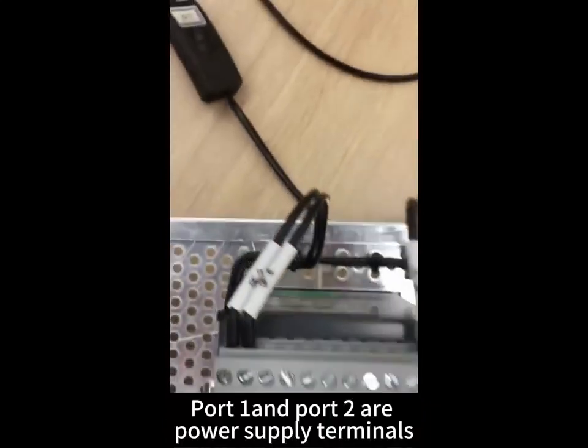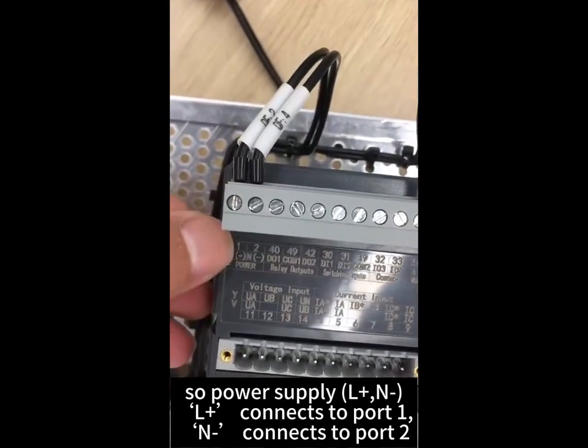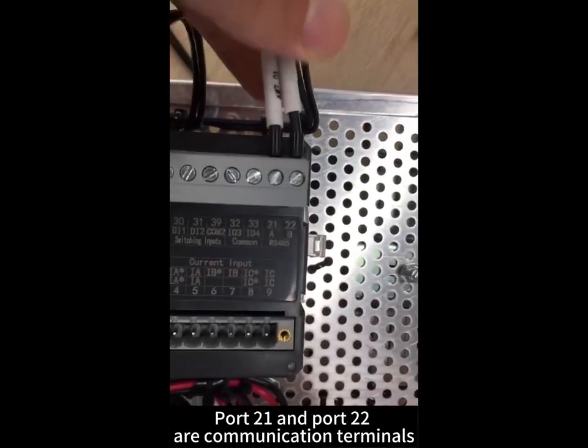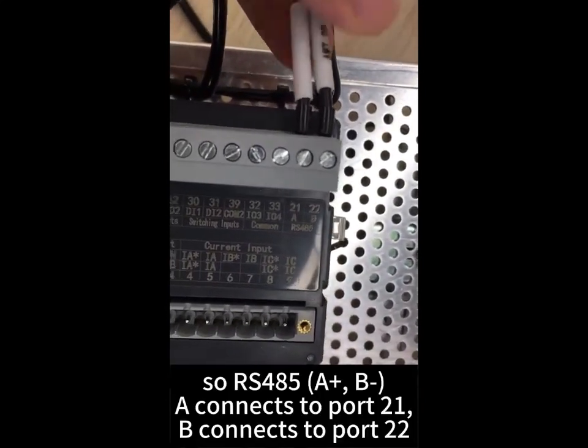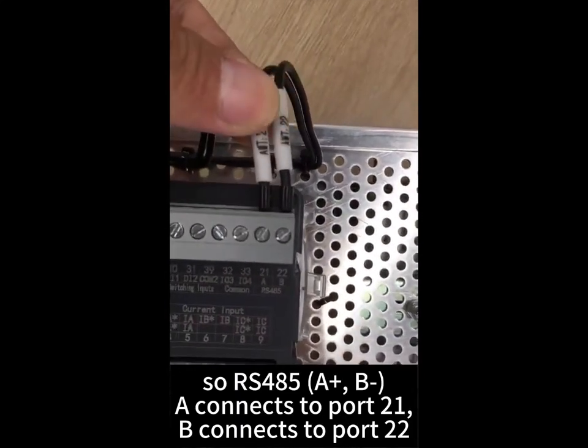Port 1 and port 2 are power supply terminals, so power supply L plus connects to port 1 and N minus connects to port 2. Port 21 and port 22 are communication terminals, so RS-485 A plus connects to port 21 and B connects to port 22.